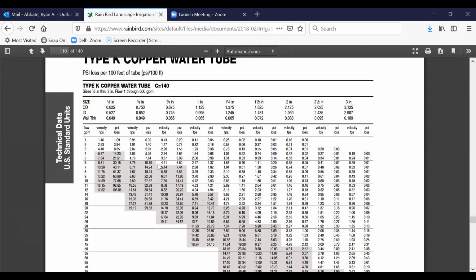With this chart, we're going to get away with 7.5 feet per second. We don't want to exceed 7.5 feet per second, so we're looking here. We could get 7.35, but the next flow, 11, brings us to 8.08 feet per second.